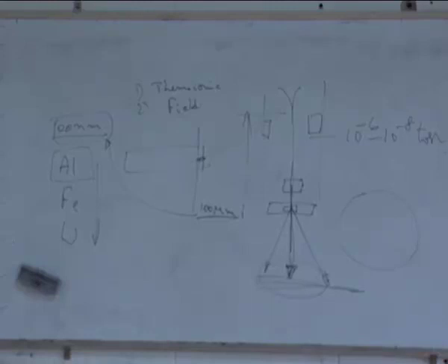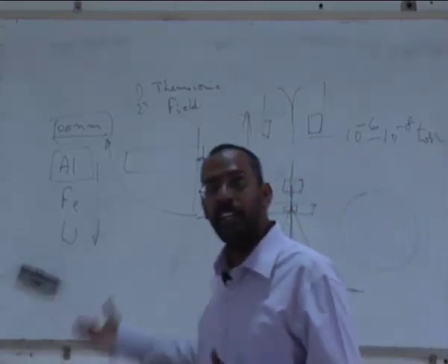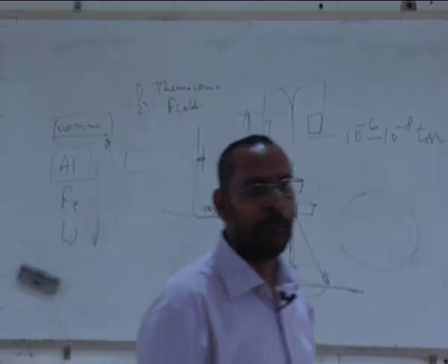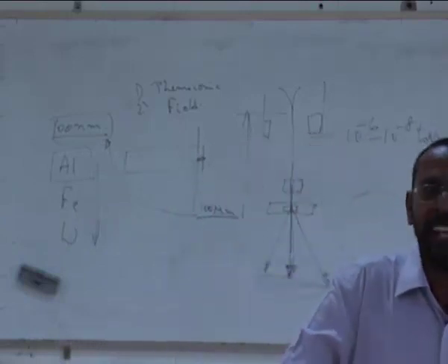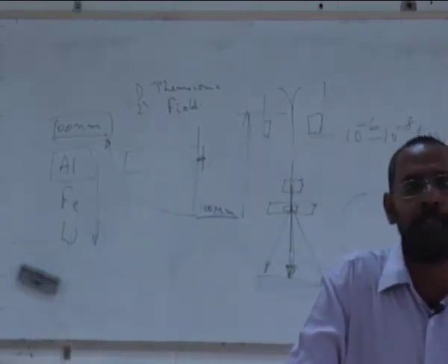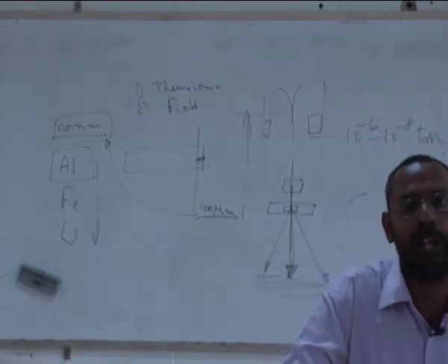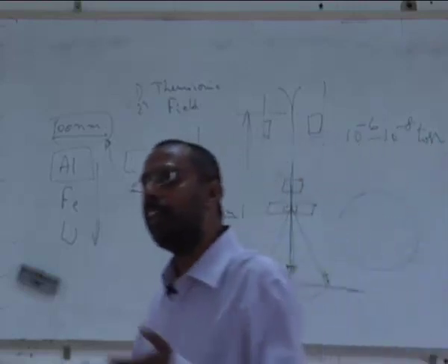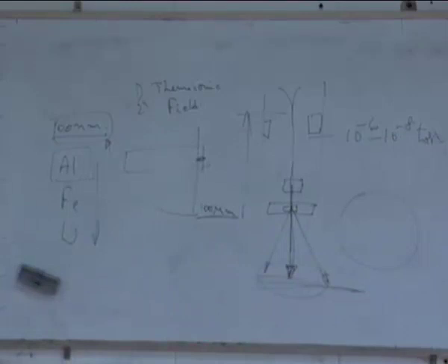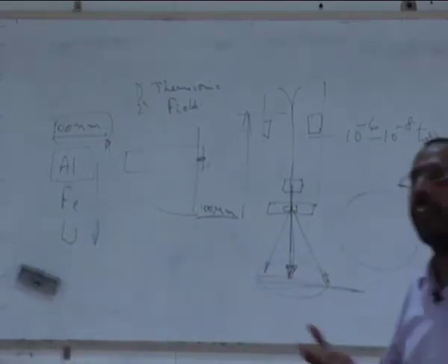So as a result, when I am looking at the sample inside the electron microscope, I may start possibly with an annealed sample, but I am now seeing a sample with a lot of dislocations. I really get confused. Where are these dislocations coming from? And you would know that it is actually because of your sample cutting, if you have not maintained a very slow speed and very low temperatures, particularly for dislocations not to be created. Otherwise you end up with this.